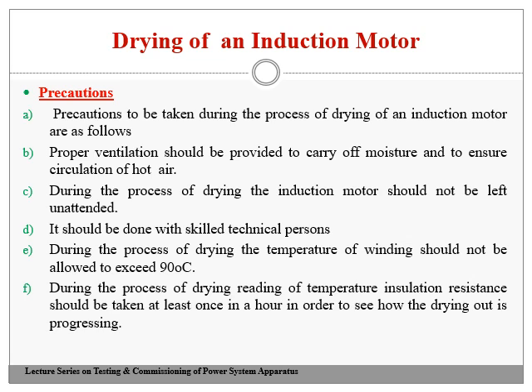Precautions. Let us see what precautions we need to take for the drying process. The precautionary measures to be taken during the drying of an induction motor are as follows. Proper ventilation should be provided to carry off the moisture and ensure the circulation of hot air. That is, if you want to do any drying process, the equipment must be properly ventilated so that it can carry off the moisture content and ensure circulation of hot air.